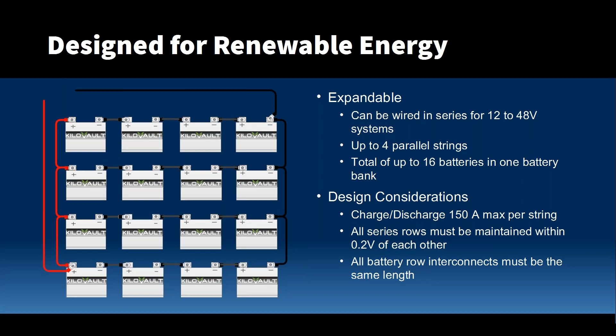And keep in mind that the charge or discharge current I mentioned on the previous slide is additive per string. So it's actually 150 amps of allowable charge or discharge current per string, which basically means that these batteries could work with incredibly large inverter systems or PV arrays and multiple stacked charge controllers without issue. And just like a lead acid bank, when you're installing the system, it's important to ensure that the interconnect cables, parallel cables, and home run cables are the same length as one another. And when initially commissioning the system, ensure that each battery is within 0.2 volts of those in the same series string.